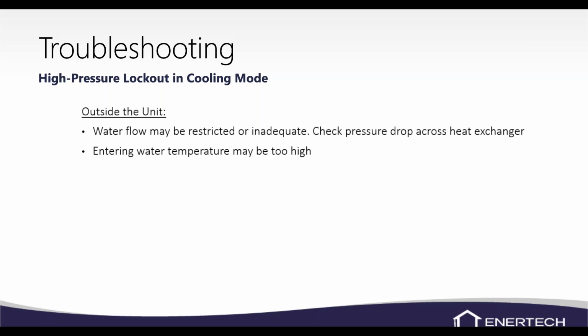You could have entering water temperature that's too high. If it's late in the year, it's been 100 degrees for a month, your ground temperature could be getting pretty warm, especially on a horizontal loop field, and your entering water temperature could be getting too high. About the max entering water temperature that we can really deal with is about 110 degrees.